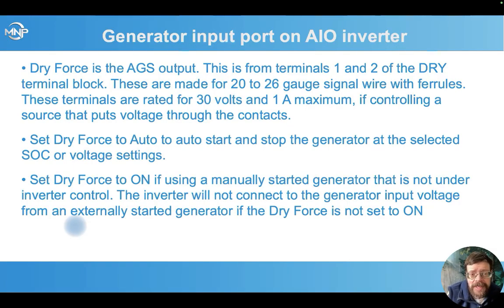Dry force is your AGS output, and this is terminals 1 and 2 of the dry force terminal block. These are made for 20 gauge to 26 gauge signal wire with ferrules on it. You can use small gauge solid wire like thermostat wire, but they don't work as well in these terminals as ferrules on stranded wire. And stranded wire without ferrules is very difficult to use. So it's about $30 for a tool that crimps ferrules on signal wire. So I'd highly recommend getting one of those for doing all the signal wires. If you're doing stacked inverters, you'll need those for the stacking cables as well.